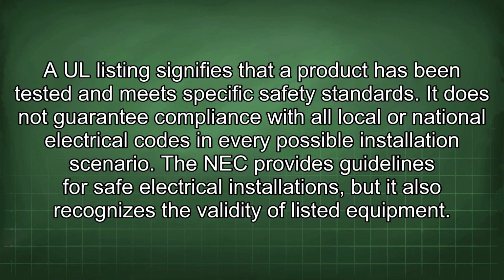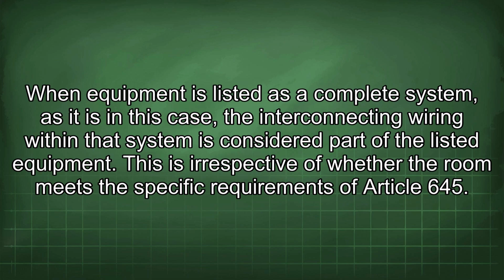A UL listing signifies that a product has been tested and meets specific safety standards. It does not guarantee compliance with all local or national electrical codes in every possible installation scenario. The NEC provides guidelines for safe electrical installations, but it also recognizes the validity of listed equipment. When equipment is listed as a complete system, as it is in this case, the interconnecting wiring within that system is considered part of the listed equipment. This is irrespective of whether the room meets the specific requirements of Article 645.